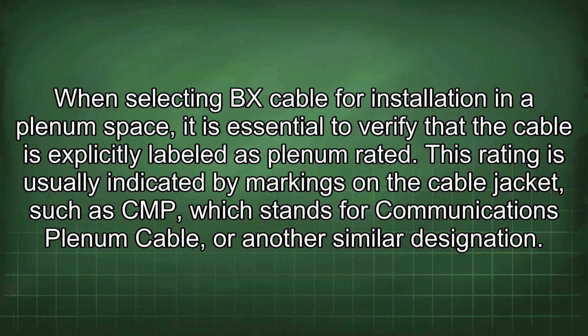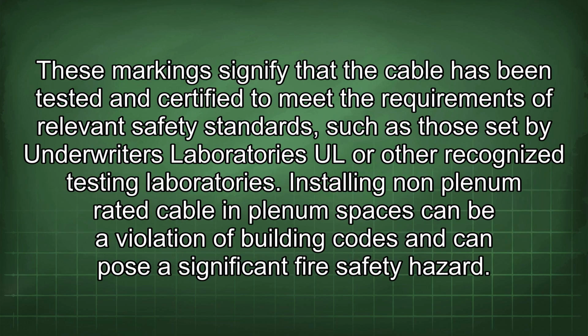When selecting BX cable for installation in a plenum space, it is essential to verify that the cable is explicitly labeled as plenum rated. This rating is usually indicated by markings on the cable jacket such as CMP, which stands for Communications Plenum Cable, or another similar designation. These markings signify that the cable has been tested and certified to meet the requirements of relevant safety standards, such as those set by Underwriters Laboratories (UL) or other recognized testing laboratories.